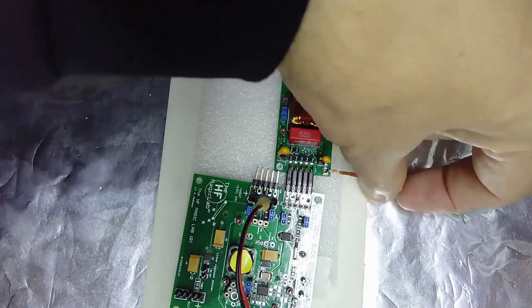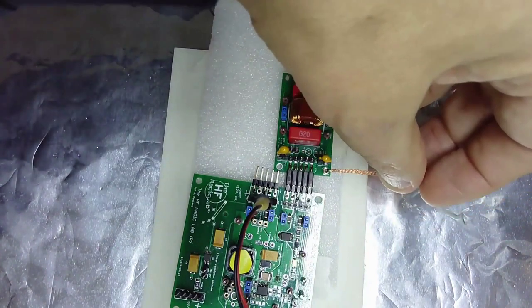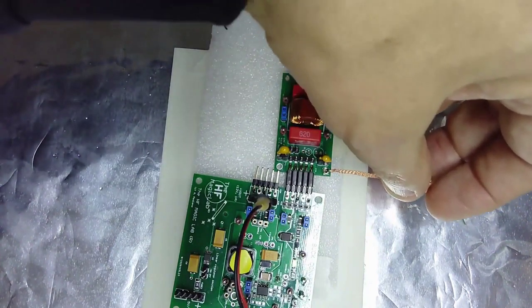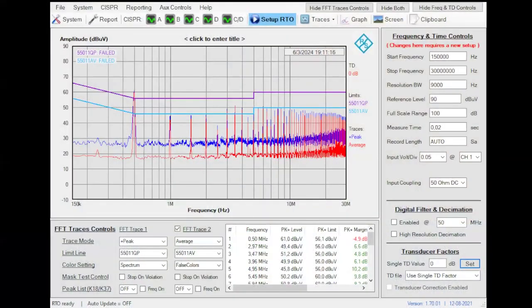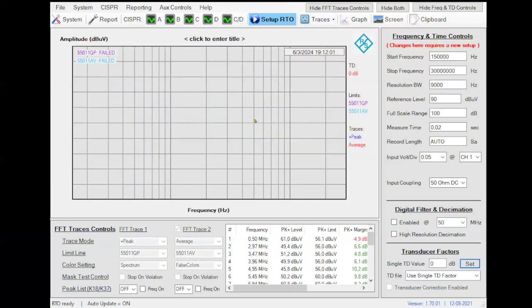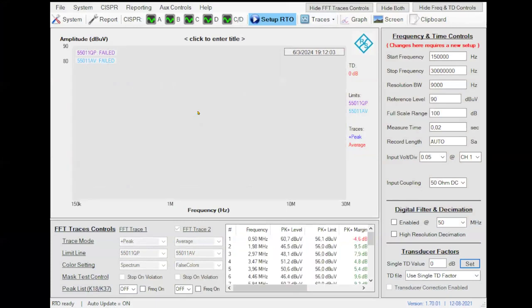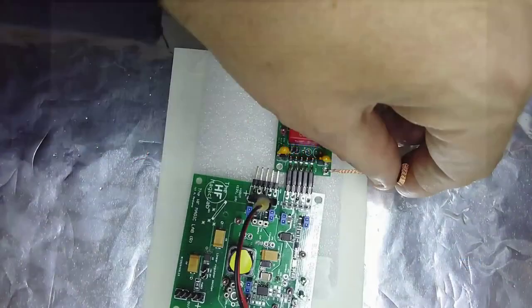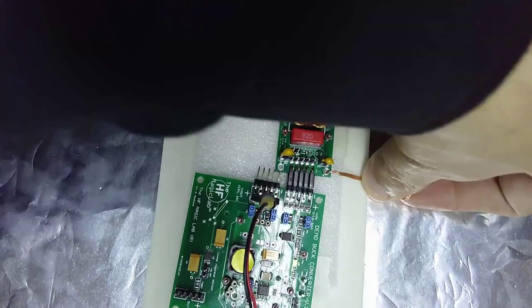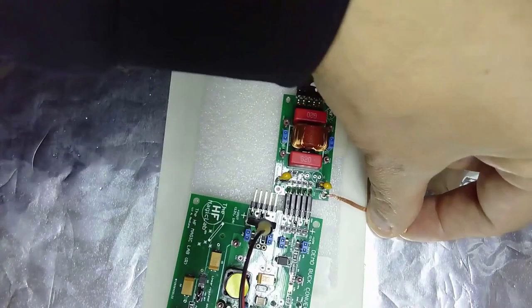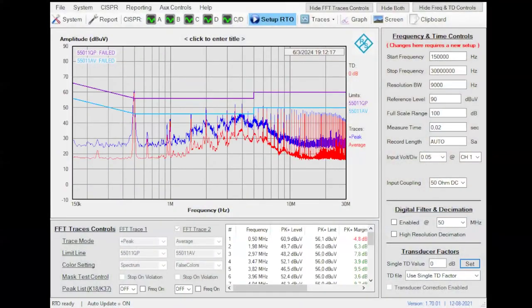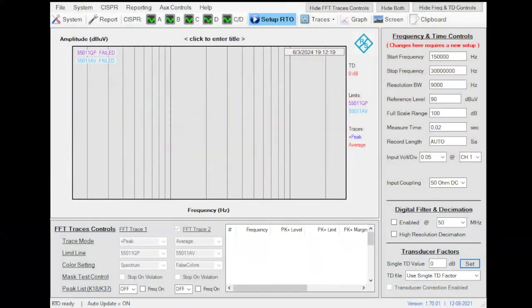So if we go to the software, let me activate the continuous update. Now the software is updating every second, okay? So now the Y capacitors are not connected this way. Now I'm going to connect in this way. Chip, chip, okay? So let's go here. And you can see here, this is not connected, Y capacitors connected.